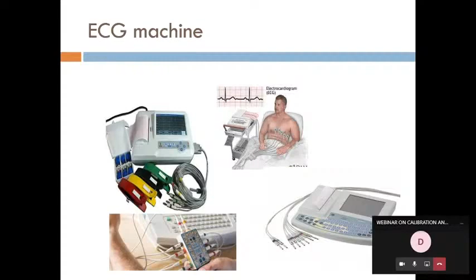Okay, first thing, you get a call from the hospital that the ECG machine is not working. First you need to check the electrodes, how the electrode contacts, everything. After that you need to check the cable. Then if everything is okay, you can open the machine and see. If not, first you need to change the electrodes. Most of the time, the problem will come with the electrodes and accessories.